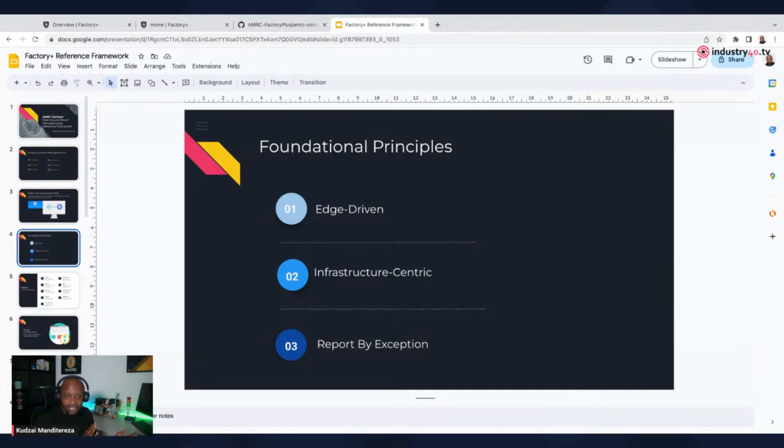Now, as I mentioned earlier, Factory Plus still uses the tried and tested methods of connecting to devices and getting data, like your poll-response protocols, such as OPC-UA and Modbus. But the idea is to keep the poll-response behavior as close to the edge as possible. So you've got your edge of network node connected to these PLCs and legacy request-response protocols, doing the polling.